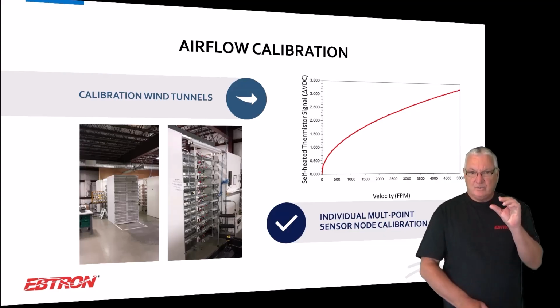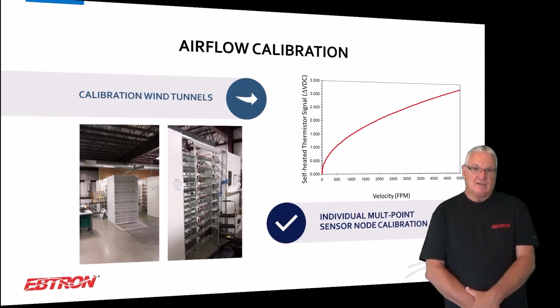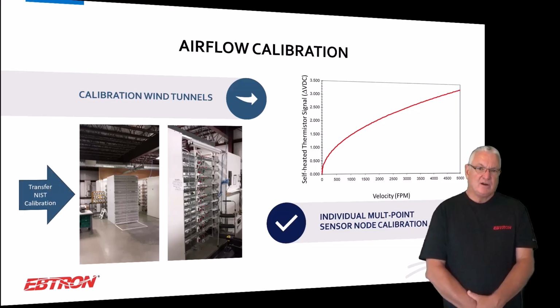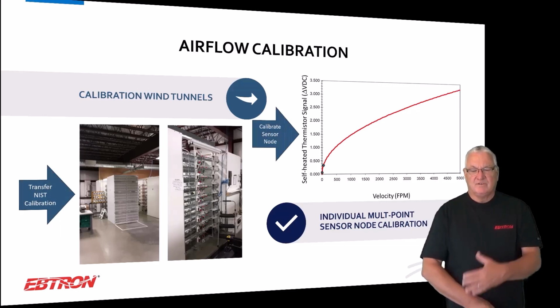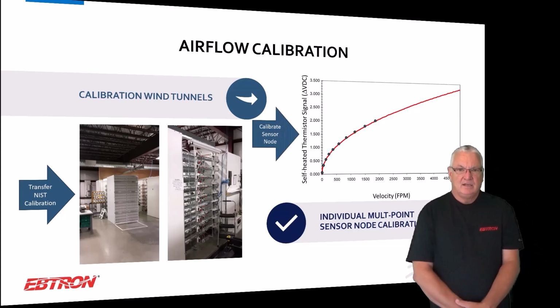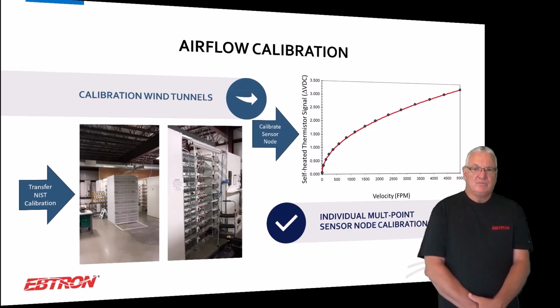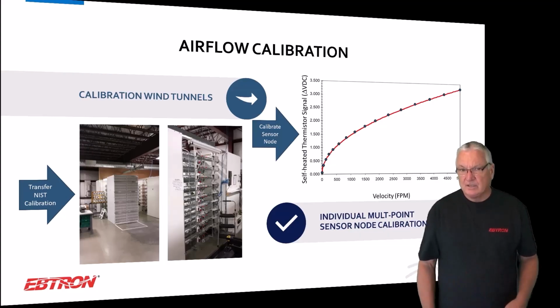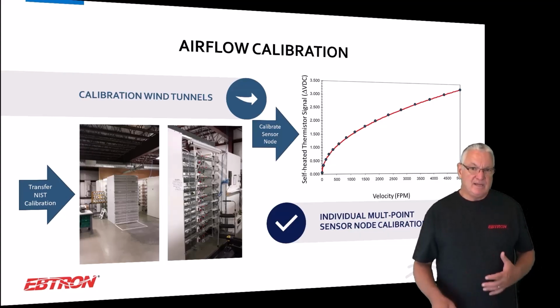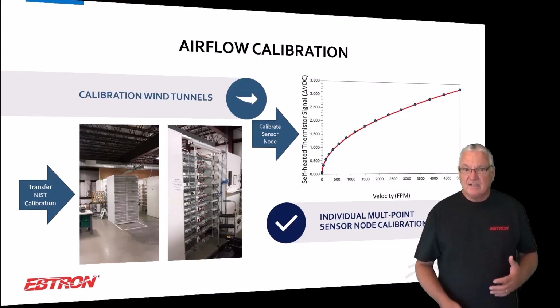So each individual one, okay? So we calibrate them in these tunnels. I'm showing our probe design right now. So in terms of the number of points and things like that, we'll calibrate our typical probe thermistor sensor nodes at 15 airflow rates plus 0, so 16 points, between 0 and 5,000 feet per minute, each individual one, okay?